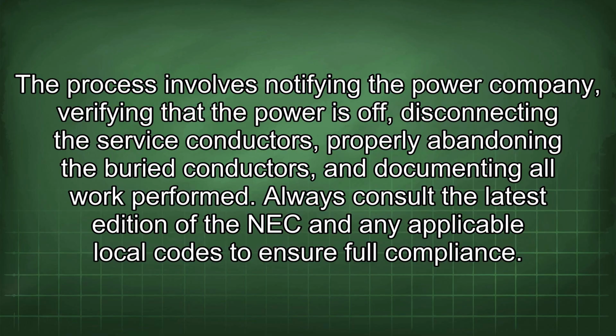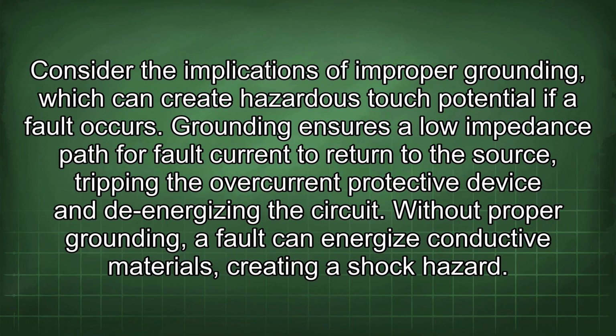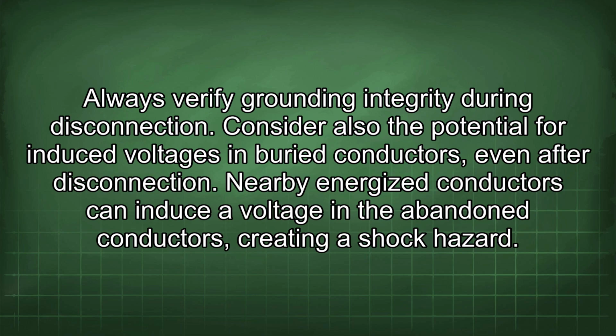Always consult the latest edition of the NEC and any applicable local codes to ensure full compliance. Consider the implications of improper grounding, which can create hazardous touch potential if a fault occurs. Grounding ensures a low impedance path for fault current to return to the source, tripping the overcurrent protective device and de-energizing the circuit. Without proper grounding, a fault can energize conductive materials, creating a shock hazard. Always verify grounding integrity during disconnection.